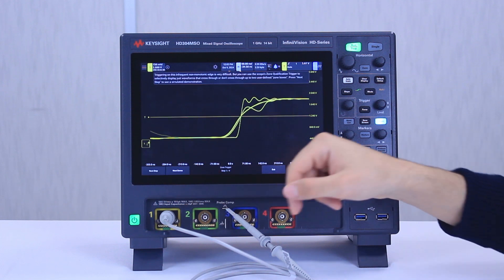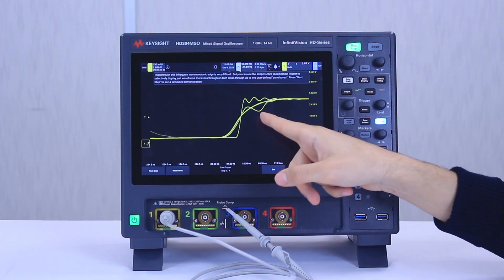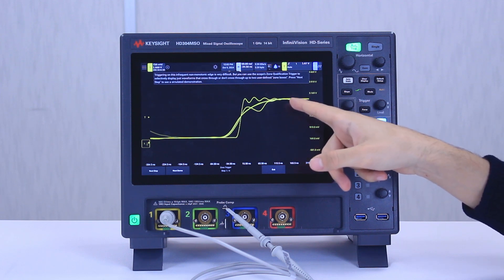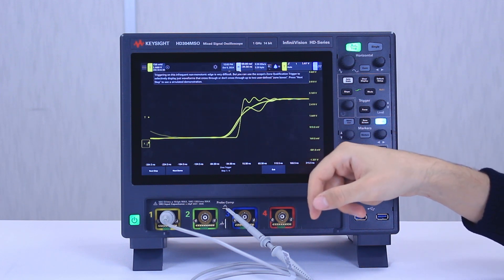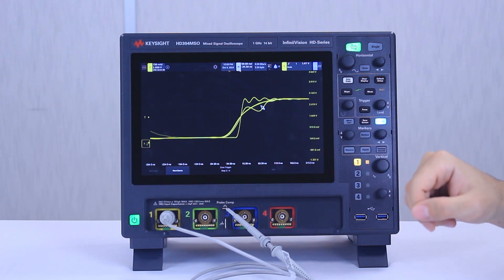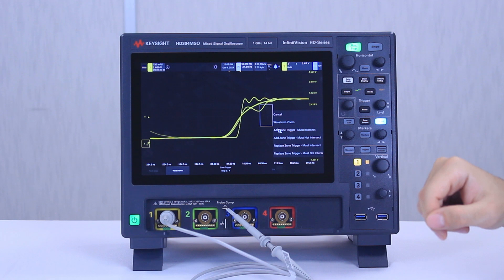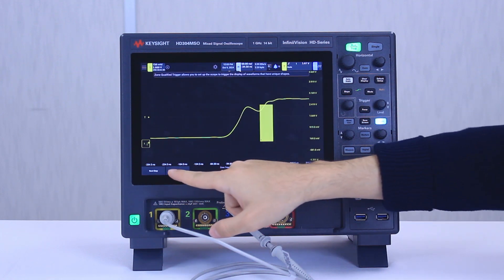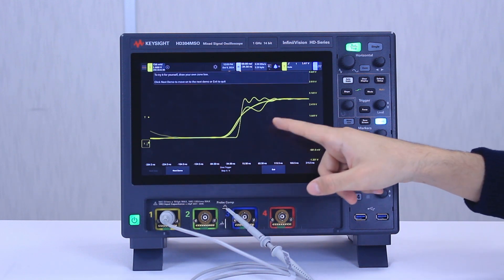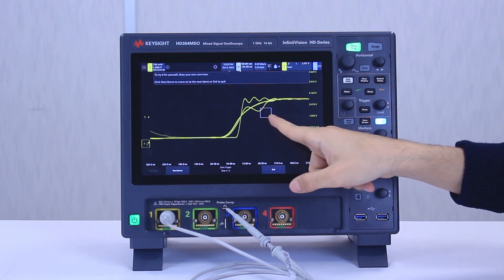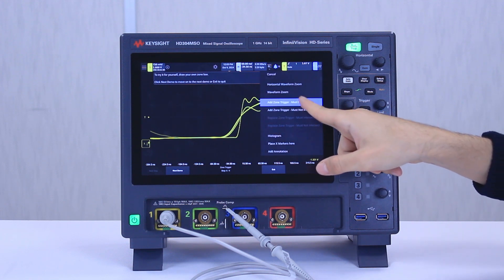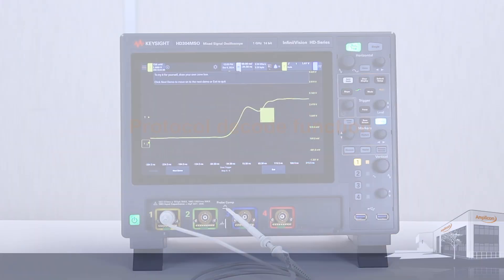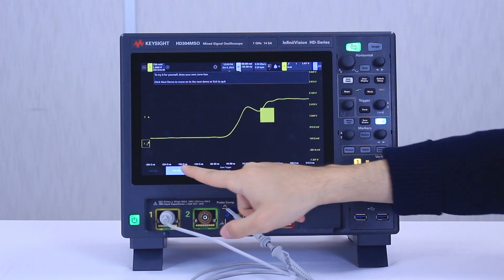Now we can do a demonstration on the zone trigger. You can see a more complex signal on the screen with some crosstalk, and I want to isolate different parts of the signal to characterize it. If we press next step, you can see a box being drawn on the part we're interested in with a must-intersect selection. We can draw this box on the screen and select must intersect to isolate the signal like that.